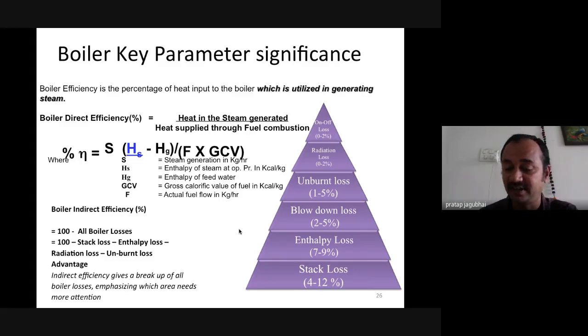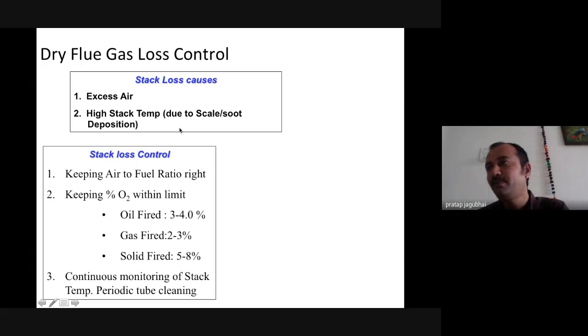How, that we will see later. So to improve more on the combustion control side, we need to have dry flue gas control. At the bottom of the pyramid, we have seen that the major chunk of the loss is the stack loss, which is called the dry flue gas loss. The dry flue gas loss is a composition of the excess air, the oxygen percentage leaving the furnace, and the higher stack temperature.